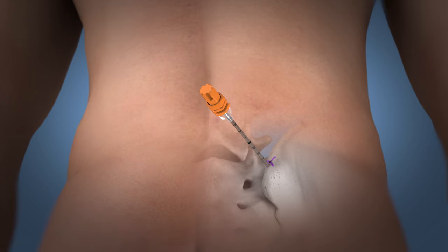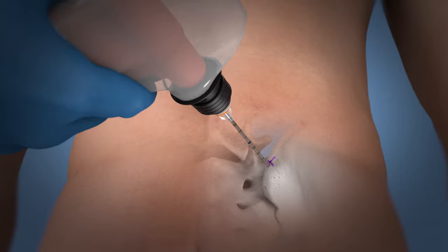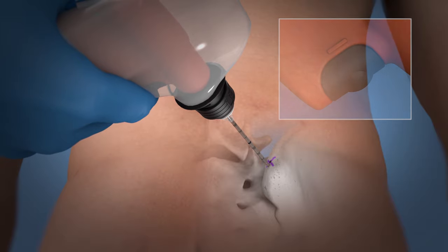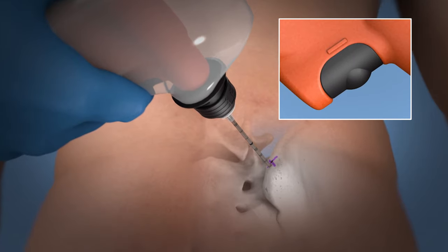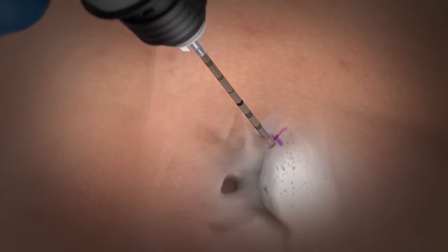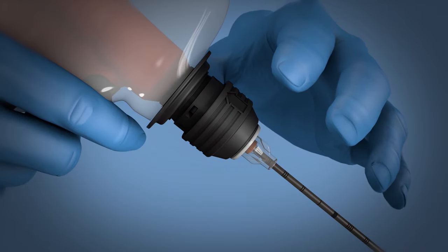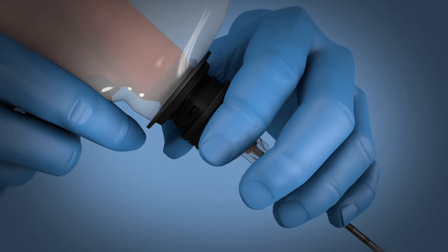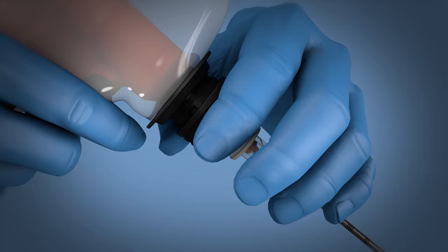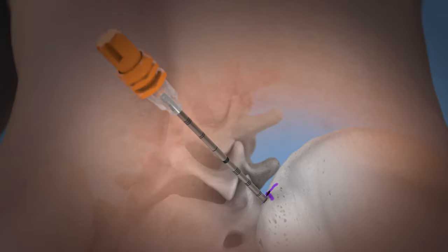Gently attach the On-Control driver until an audible click is heard, which indicates attachment. Engage the driver trigger continuously with one to two pounds of downward pressure until the cortex is penetrated. Disconnect the driver from the needle by lifting up the black collar on the connector and lifting the driver up and off of the needle hub without dislodging the needle. Gently twist and lift the stylet out of the cannula.